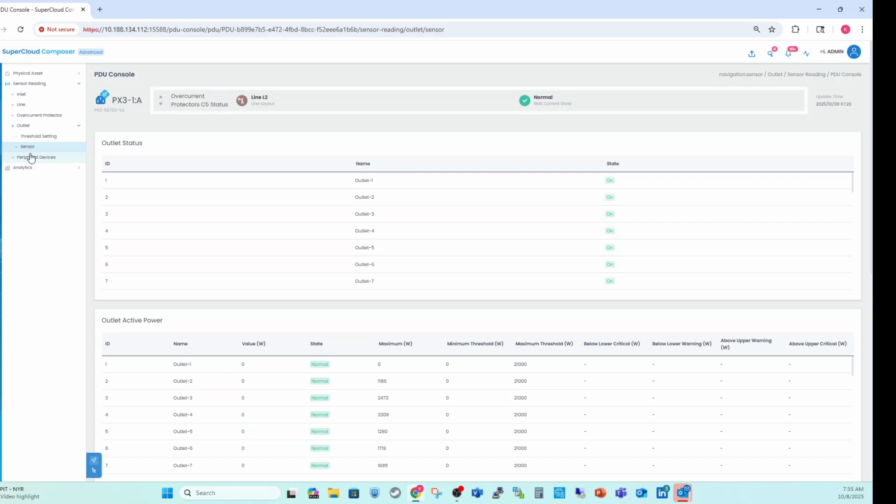Let me also mention, and I talked about this in previous videos, some of the PDU manufacturers are still sort of stuck on the SNMP, which required us to create that universal agent descriptor to be able to provide and pull this information. So of course, we're using the SNMP walk to provide those data elements from the OID, and then basically provide that in a RESTful API based on Redfish.